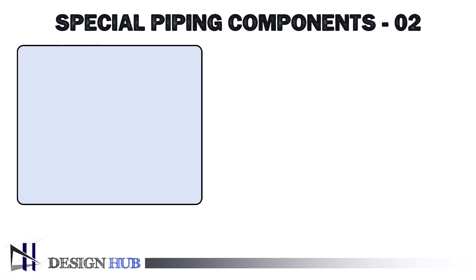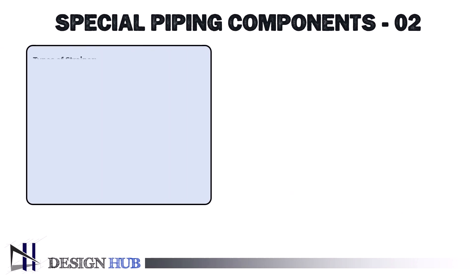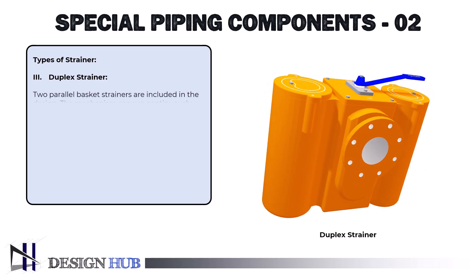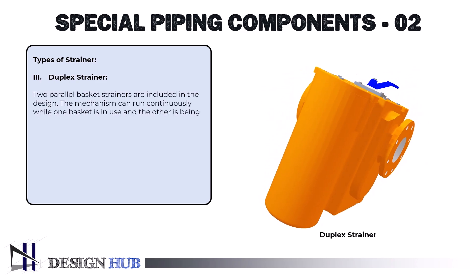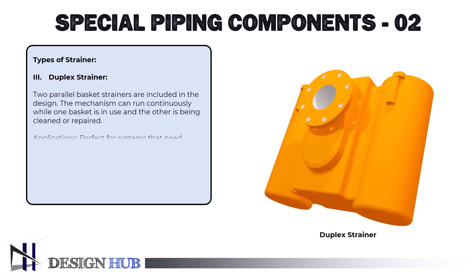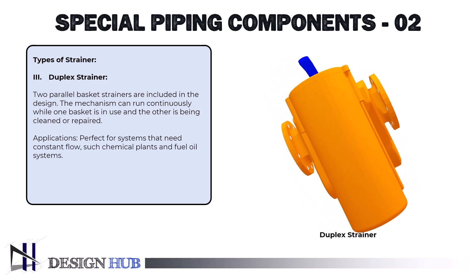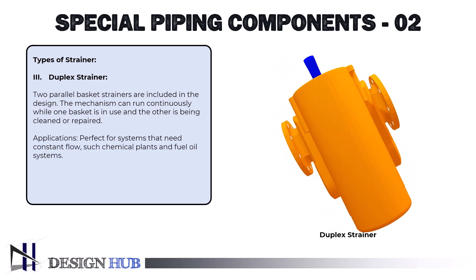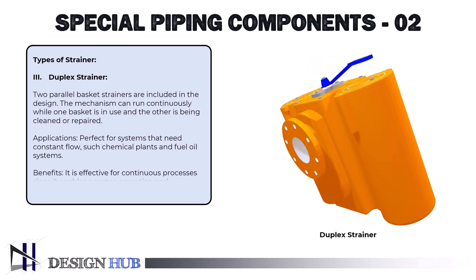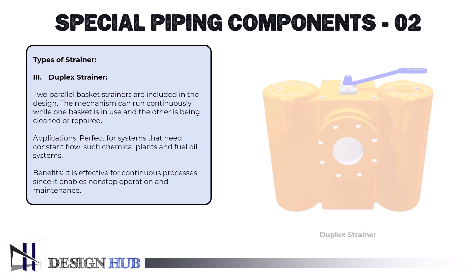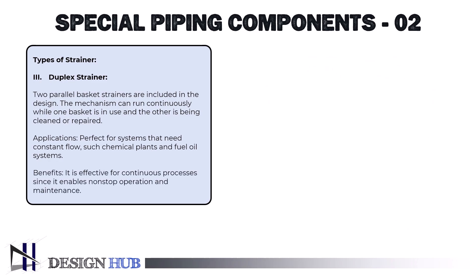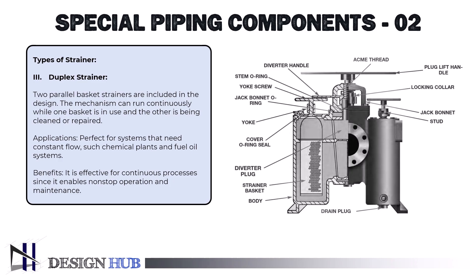The third one is a duplex strainer. Two parallel basket strainers are included in the design. The mechanism can run continuously while one basket is in use and the other is being cleaned or repaired. Applications: perfect for systems that need constant flow, such as chemical plants and fuel oil systems. Benefits: it enables non-stop operation and maintenance, making it effective for continuous processes.